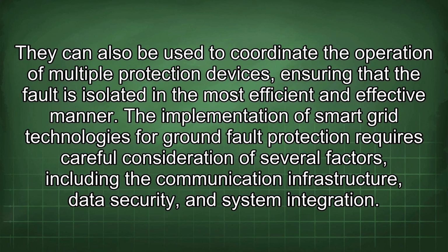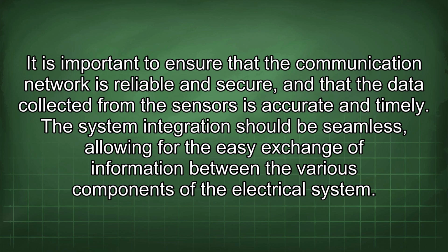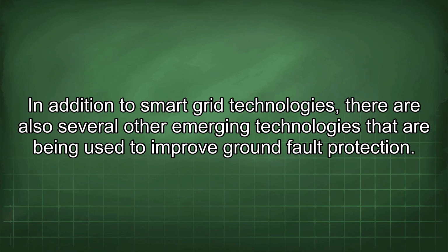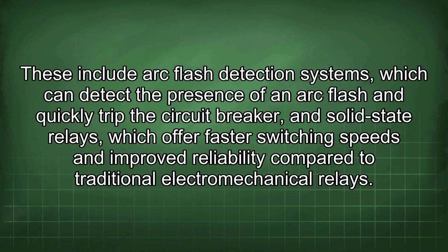The implementation of smart grid technologies for ground fault protection requires careful consideration of several factors, including the communication infrastructure, data security, and system integration. It is important to ensure that the communication network is reliable and secure, and that the data collected from the sensors is accurate and timely. The system integration should be seamless, allowing for the easy exchange of information between the various components of the electrical system. In addition to smart grid technologies, there are also several other emerging technologies that are being used to improve ground fault protection. These include arc flash detection systems, which can detect the presence of an arc flash and quickly trip the circuit breaker, and solid-state relays, which offer faster switching speeds and improved reliability compared to traditional electromechanical relays.